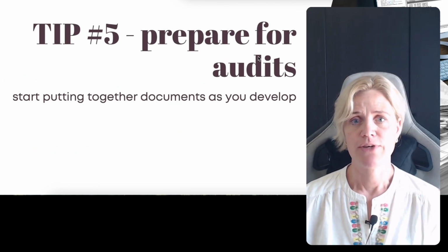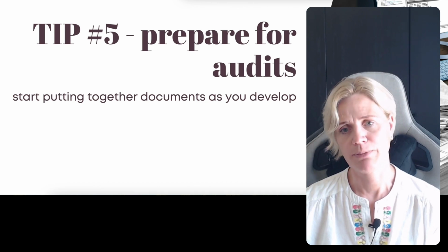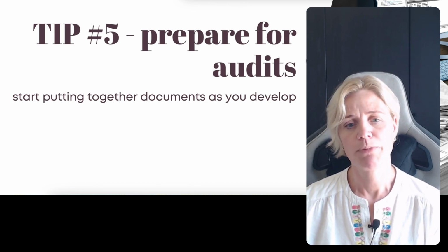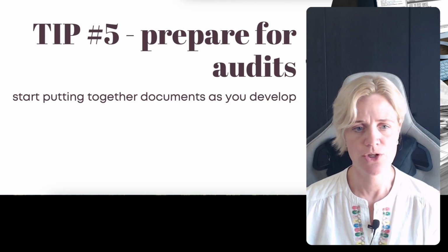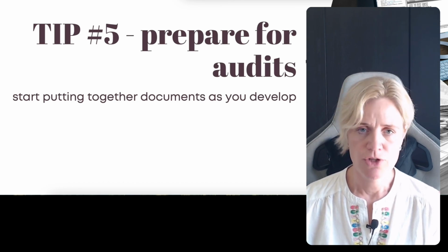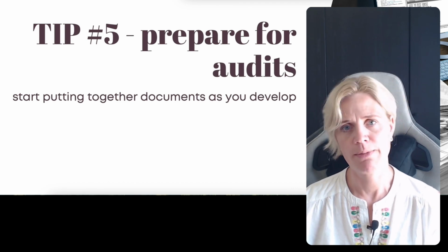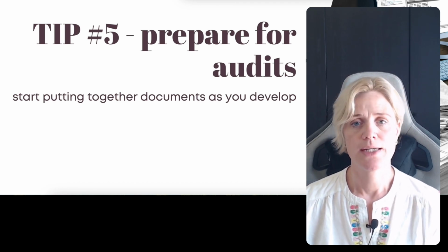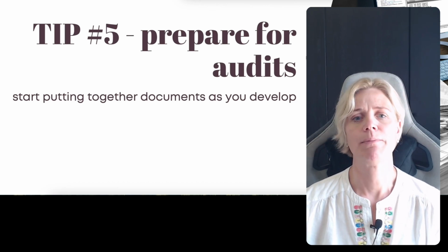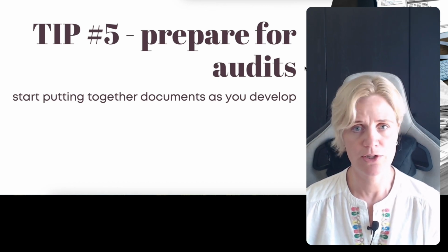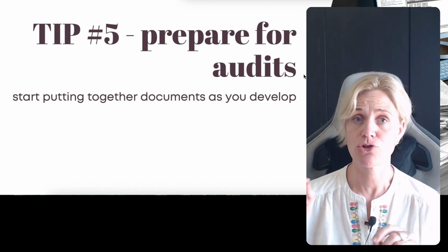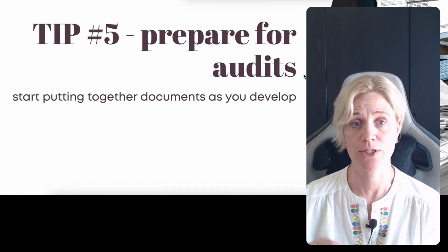That really helps. Matteo Gubellini, our own regulatory affairs manager, says that one thing that he sees all the time is that companies scramble late and suffer for it. Prepare for it. Take the time. Start putting together your documents as you develop. If you don't know where to start, start with the intended use. Build everything up from there: user needs, requirements, risks, and so on. Use guidance documents. There are plenty of them for medical devices, and go through the notified body guidance documents as well, especially ones that actually detail how to structure your documentation according to their preference.